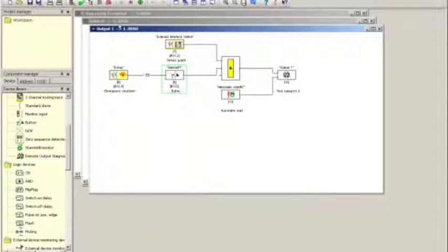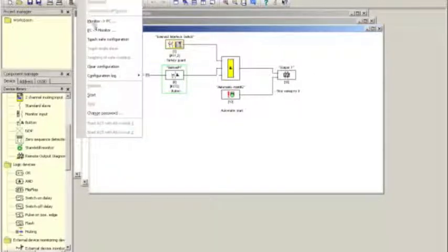So when that signal is connected to 24 volts by virtue of a button or perhaps from a PLC, whatever you select to do, then the door switch will be unlocked because power is applied to the solenoid, and now the key can be removed, which is equivalent to opening the door. Okay, that's really the only change here. So let's go and download this to the monitor as before.